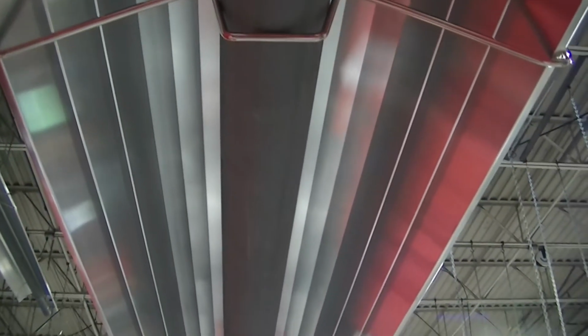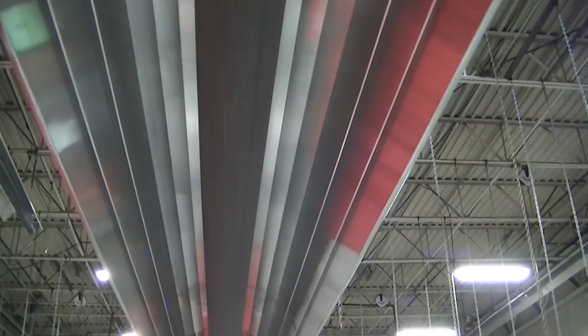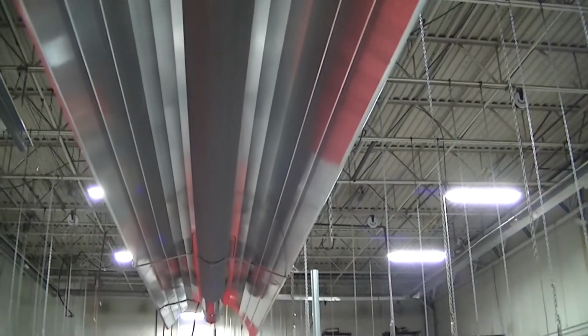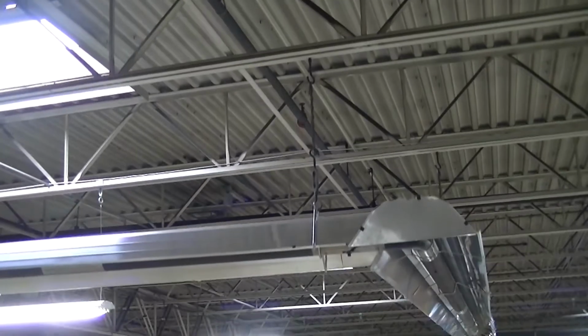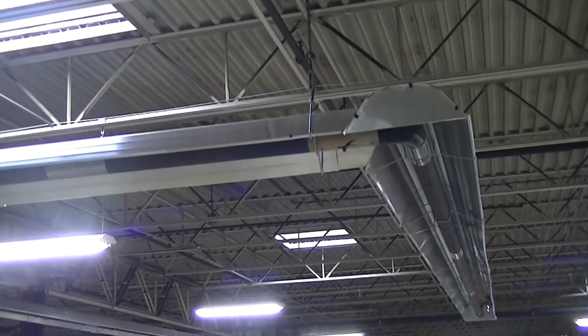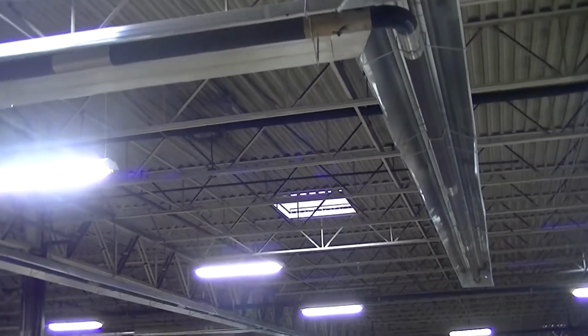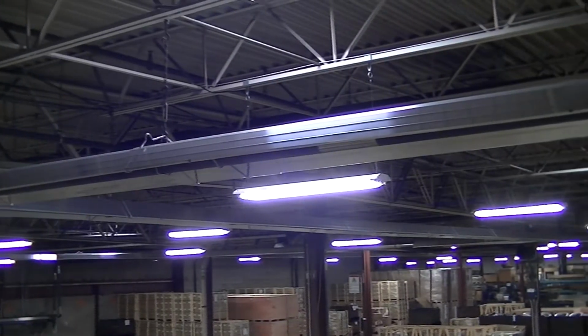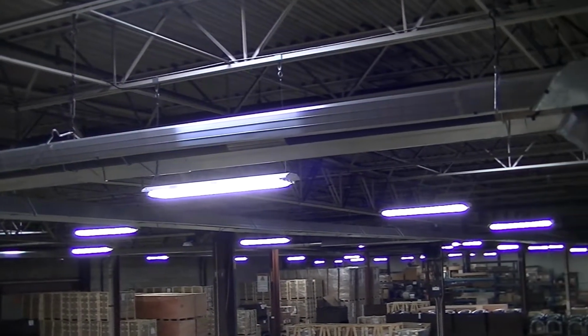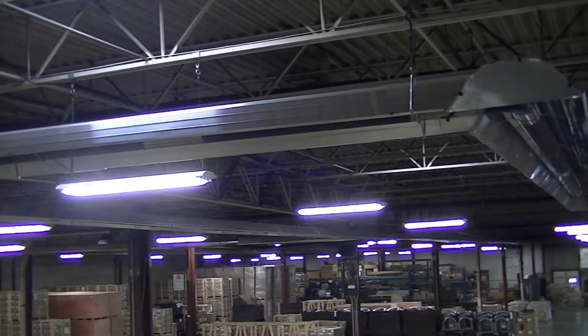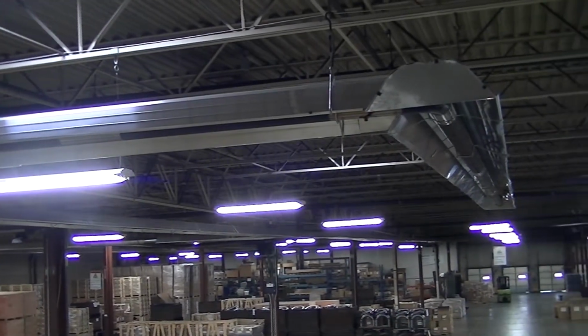Make sure the following items are installed correctly: hangers, reflector supports, reflectors. Also, make sure radiant and tailpipe tubes are installed at the proper pitch per the installation, operation, and service manual. Move on to the next step after properly installing the equipment.